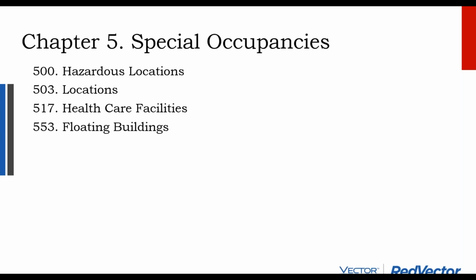Okay, so that's pretty much it for section 480. It's a very short section, and most of the robust battery requirements are being migrated towards the more specialty sections towards the back. With electric code, the general rules sections end at chapter 4, and then we get to chapter 5, where we start to get into specialty requirements. So chapters 1 through 4 are to do with services and feeders and the wires and cables themselves, and then general equipment like air conditioners and lights and dishwashers and appliances, stuff that's just all over the place.